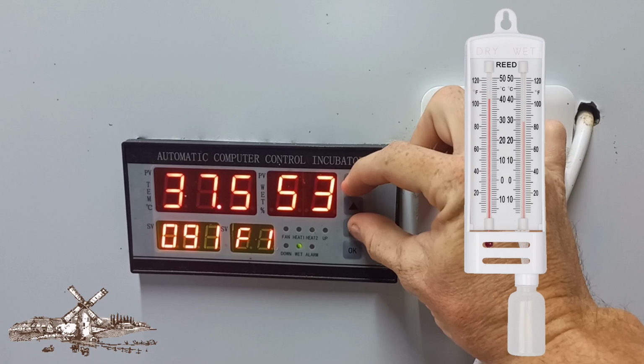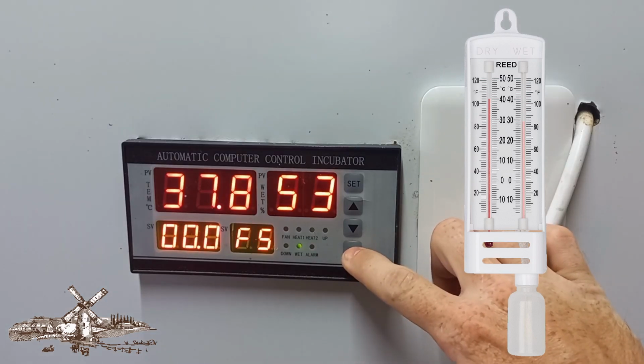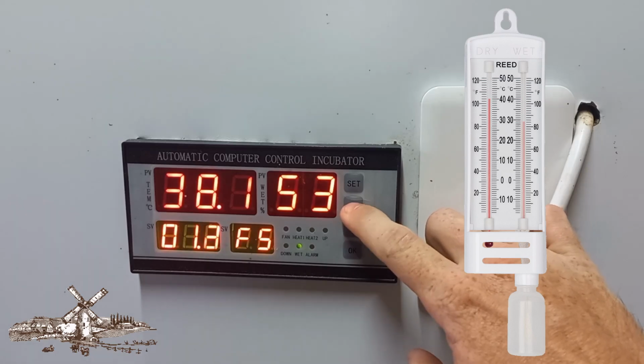Now, F1 would be the value, the 90 would be the property value, and the 90 is in fact the turning interval time. So by changing different F values, you can change how your controller behaves. But the value I'm interested in here is the F5 value, because that is my temperature calibration value. And whatever I type in here will be added to the default temperature of the controller, and it will then push the temperature measurement of my controller up. And to get to 40 degrees Celsius, I need to add 2.5 degrees. And so I'm going to push the up arrow key until the value for F5 is 2.5, and I'm then going to push OK to accept.